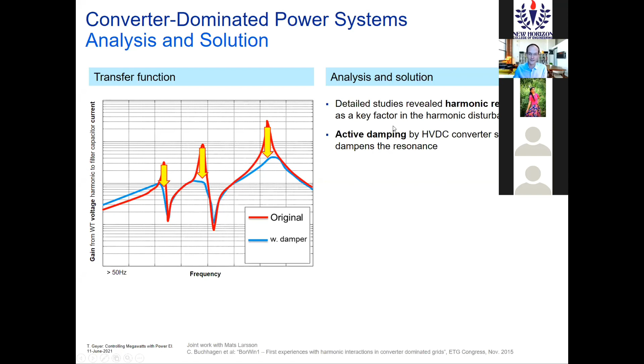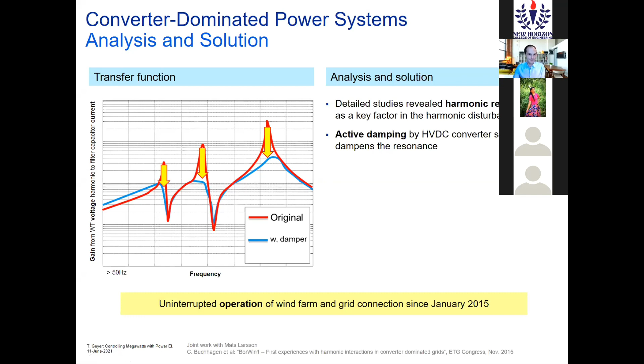What also became clear is that the biggest player is the HVDC converter. It's not that the HVDC converter caused the problems, but it's by far the biggest contributor, so it made sense for the HVDC converter to actively do something about it. We came up with a way to actively dampen these resonances using the converter, and doing that allowed us to bring down these transfer functions, effectively removing the resonances and the large currents in the filter banks.